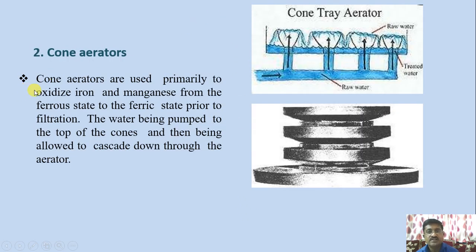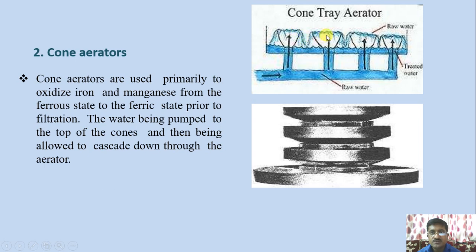Cone aerators are used primarily to oxidize iron and manganese from the ferrous state to the ferric state prior to filtration. Water is pumped to the top of the cones and allowed to cascade down through the aerator. The cone trays are flooded and water moves through the cones, being introduced as splashed water.